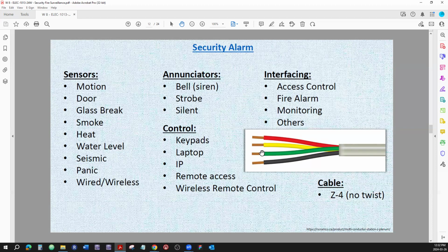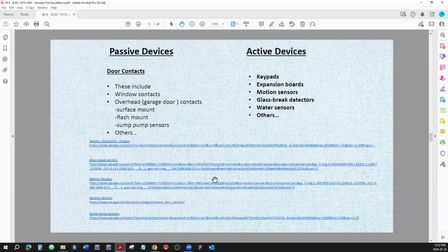With security alarm contacts, twist acts as a coil. Coils do not like change. They oppose change. So, if there's a change that happens fast enough, you can open the door and close it really quick. If the cable is long enough, the signal might never get to the zone to actually let the alarm system know that the alarm has gone off. So for that reason, the twist acts like a coil. So we want no twist in the alarm cables.